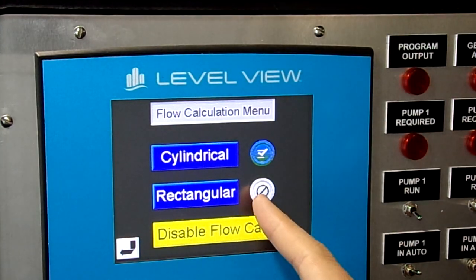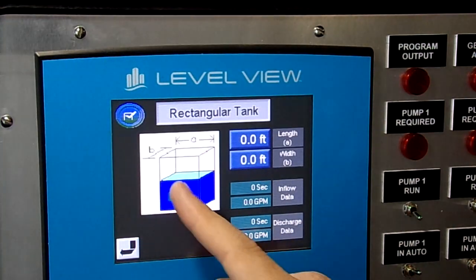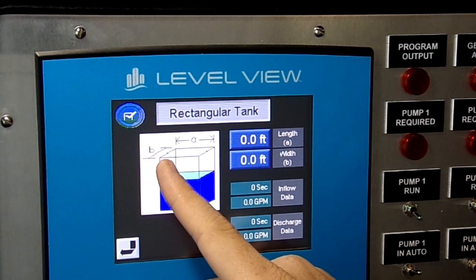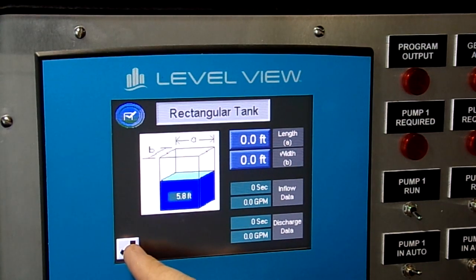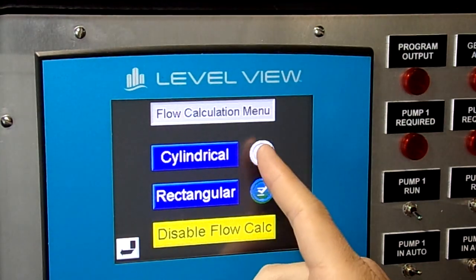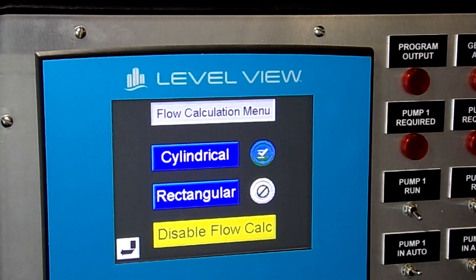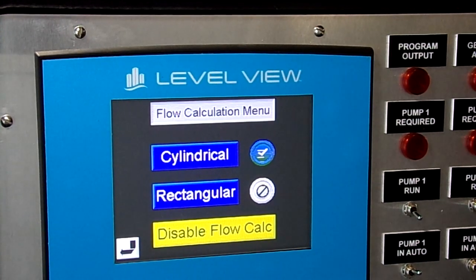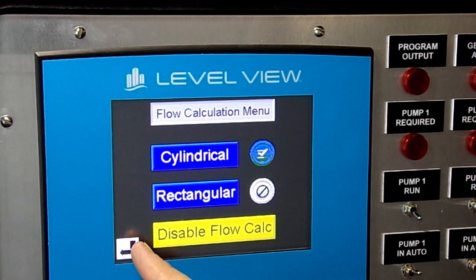And we also have the ability to do it with rectangular tanks. We just have to insert dimensions A and B. This will do volumetric flow calculations for the station to show you approximately how much flow is coming into your station. This is not for metering applications, but just for a range to give you for what we think your pumps might be doing.